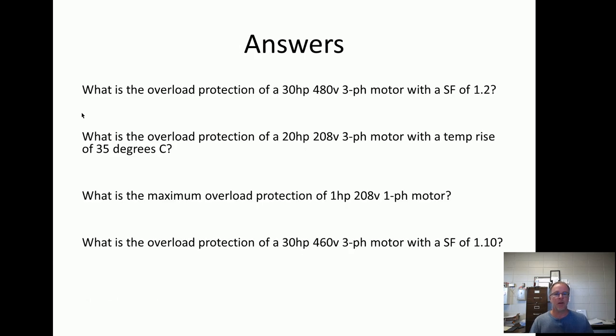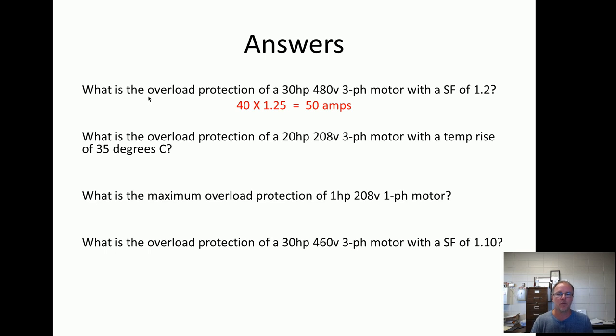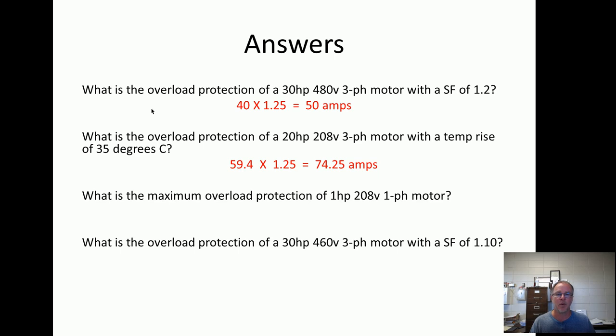Alright, we're back. The answers: a 30-horsepower, 480-volt motor with a service factor of 1.2 — full load current is 40 amps, times 1.25 because the service factor is greater than 1.15 — so it's 50 amps. The overload protection of a 20-horsepower, 208 three-phase motor with a temperature rise of 35 degrees (that's less than 40) — full load current is 59.4, times 1.25, equals 74.25 amps.